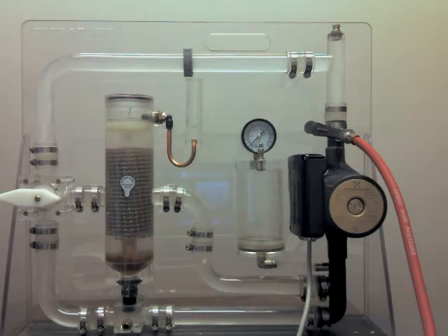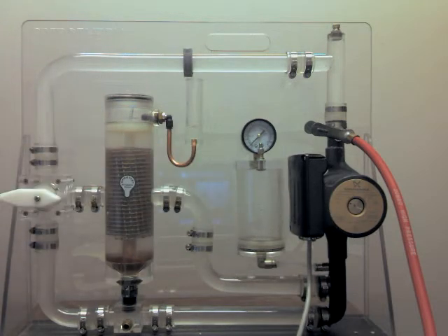The other reason why you want to get the air out of your system, besides just protecting your equipment, is air is a really good insulator. You see all these bubbles circulating through here. Anywhere in your systems that the BTUs are being exchanged, so the steam converters or chiller evaporator tubes or any kind of air handling unit coil, all those places, if you have air in there, it's slowing the heat transfer down. So it's working, but it could be working a lot faster and therefore saving you energy by just simple equipment not needing to run as often.